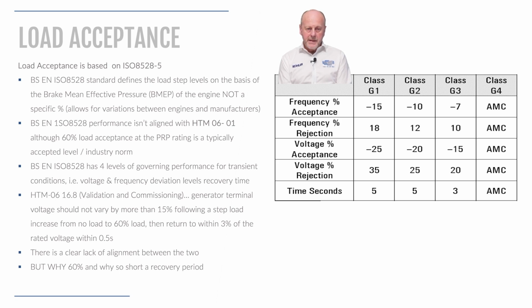In BS EN ISO 8528, we have set out 4 levels of governing performance for transient conditions, i.e. this is the level of voltage and frequency deviations that are acceptable and the stated recovery time. In HTM06, in particular 16.8, in the validation and commissioning section, generator terminal voltage should not vary by more than 15% following a step load increase from no load to 60% load and then return to within 3% of the rated voltage within 0.5 seconds.